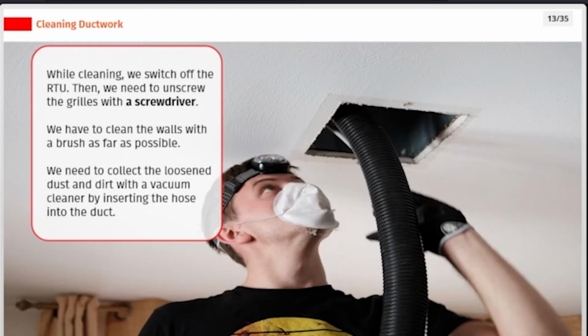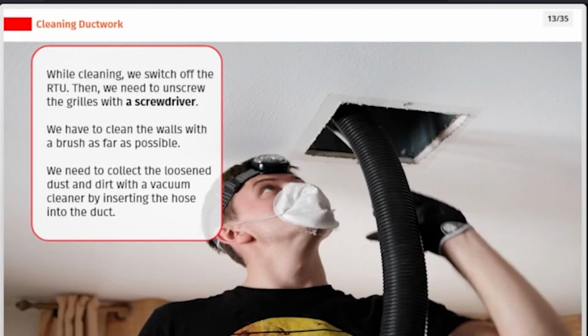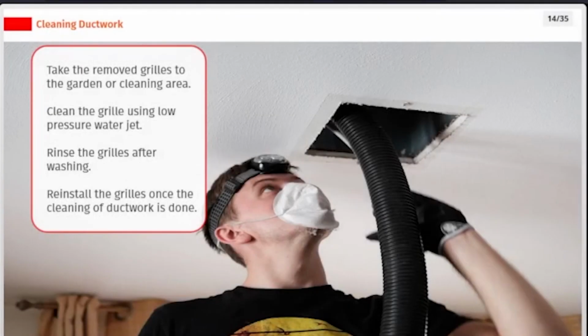While cleaning, we switch off the RTU. Then, we need to unscrew the grills with a screwdriver. We have to clean the walls with a brush as far as possible. We need to collect the loosened dust and dirt with a vacuum cleaner by inserting the hose into the duct. Take the removed grills to the garden or cleaning area. Clean the grill using a low-pressure water jet. Rinse the grills after washing. Reinstall the grills once the cleaning of the ductwork is done.